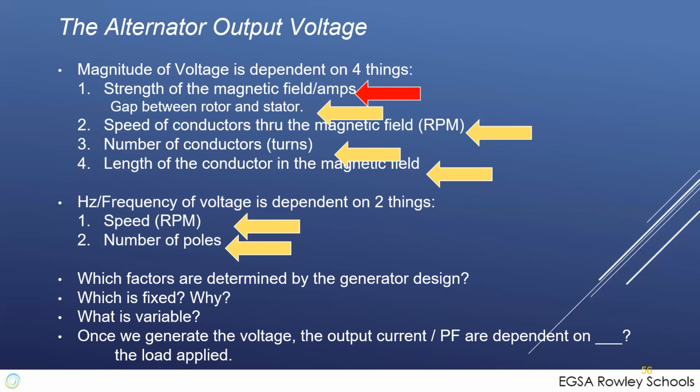And this is difficult for some customers to understand when it comes to talking about power quality, which is really going to be a concern for almost all power systems being built today. We're seeing more and more VFDs, more and more LED lighting, both of which have a lot of harmonic content, a lot of dirty, if you will, current consumption. And the customer says, well, my load works just fine on utility. Why isn't it working on your generator? What's going on here?